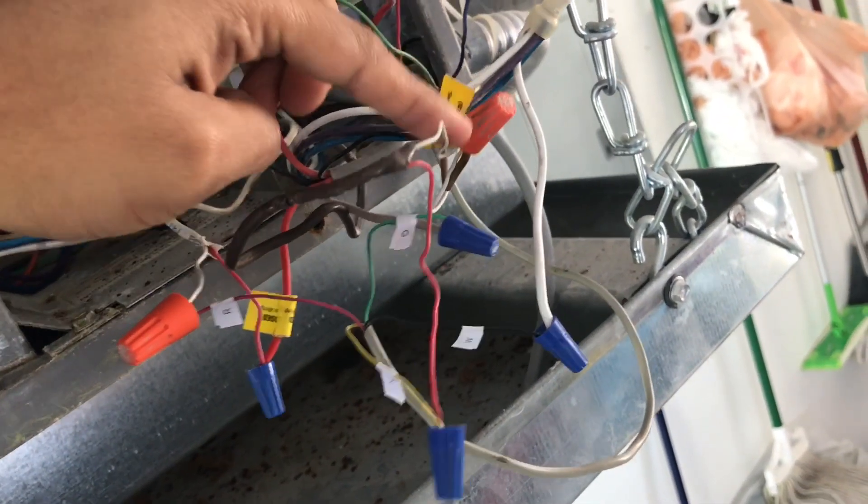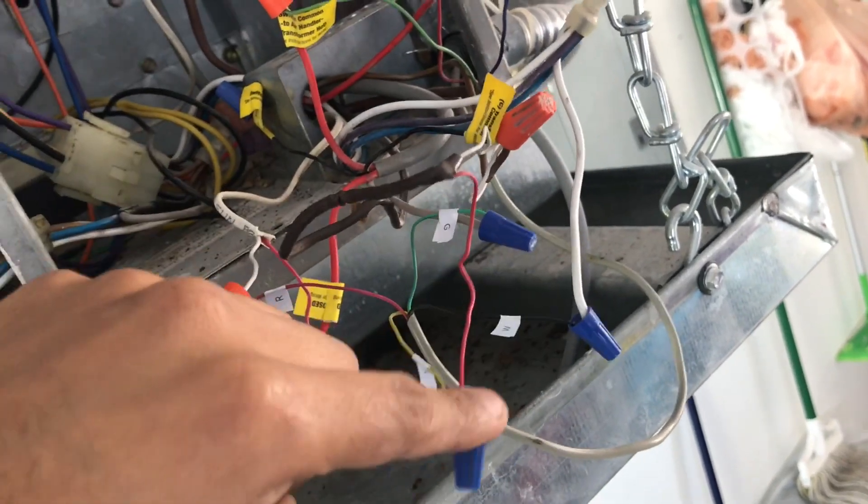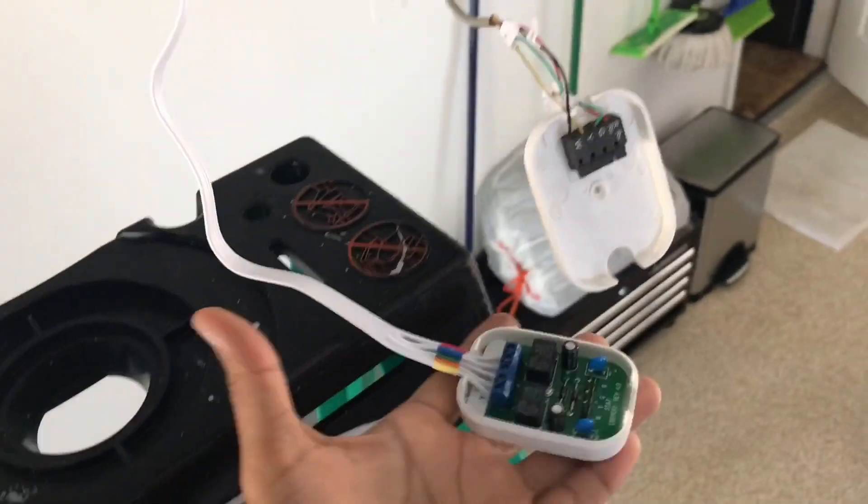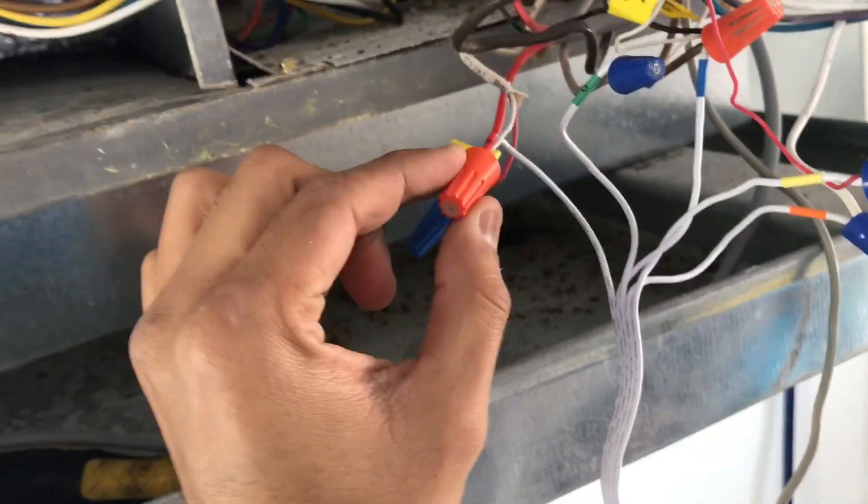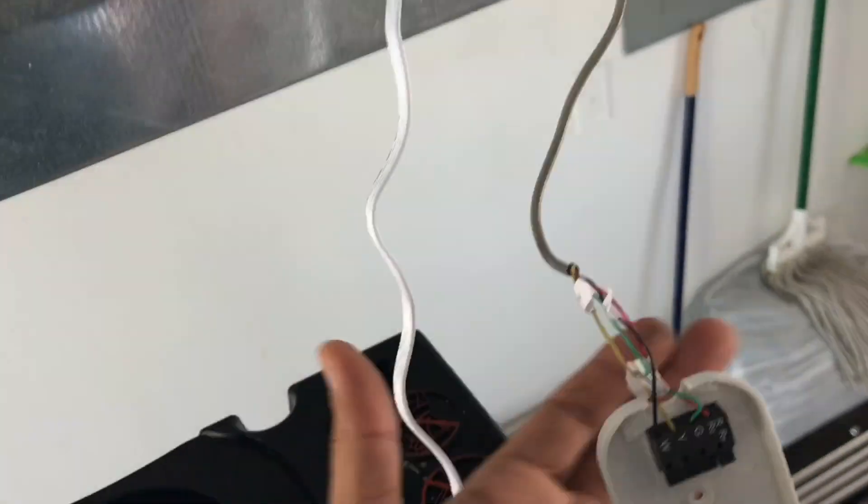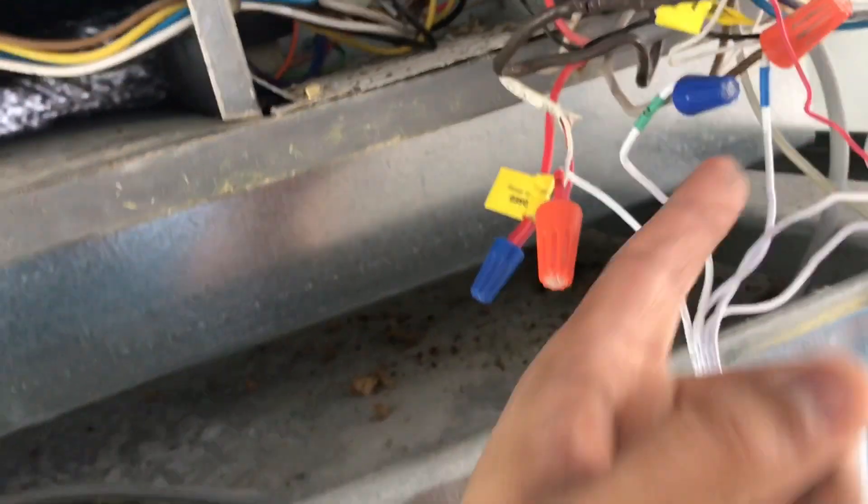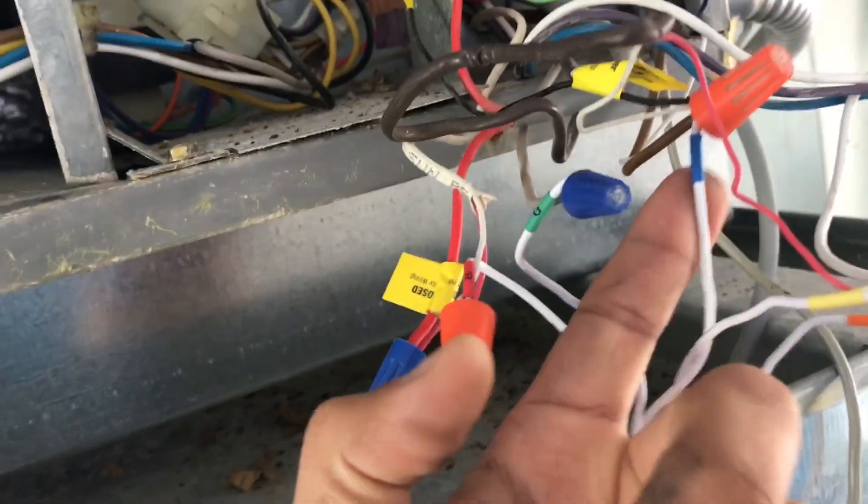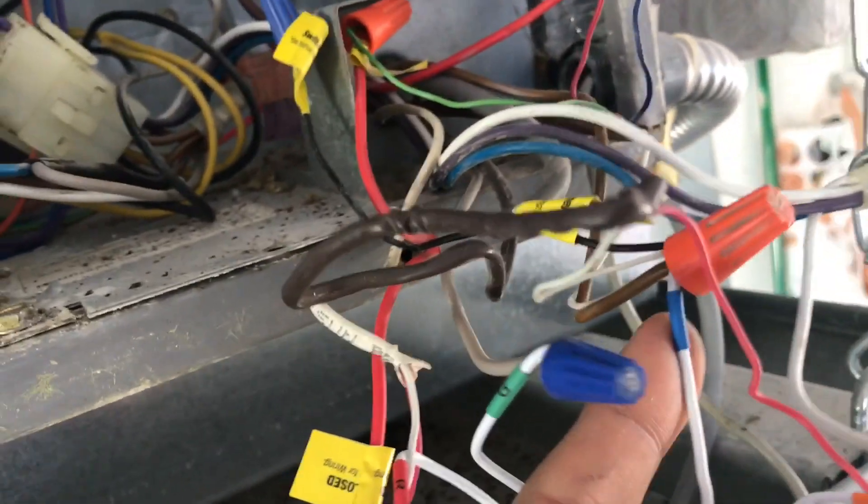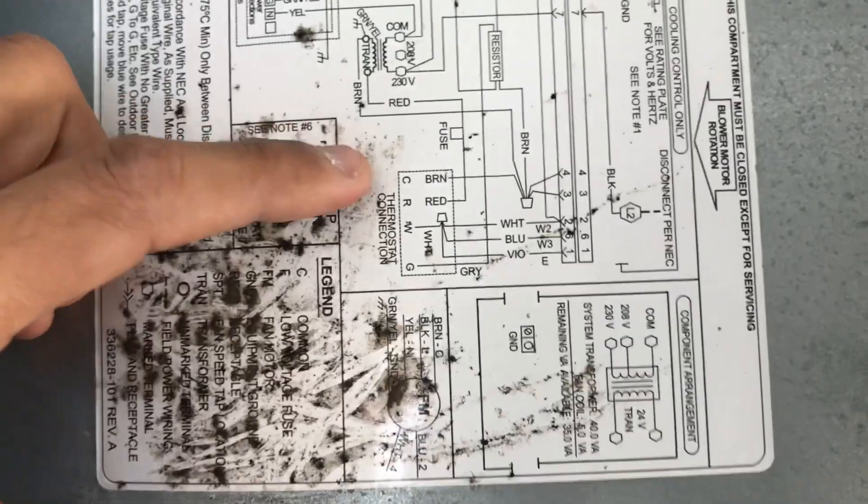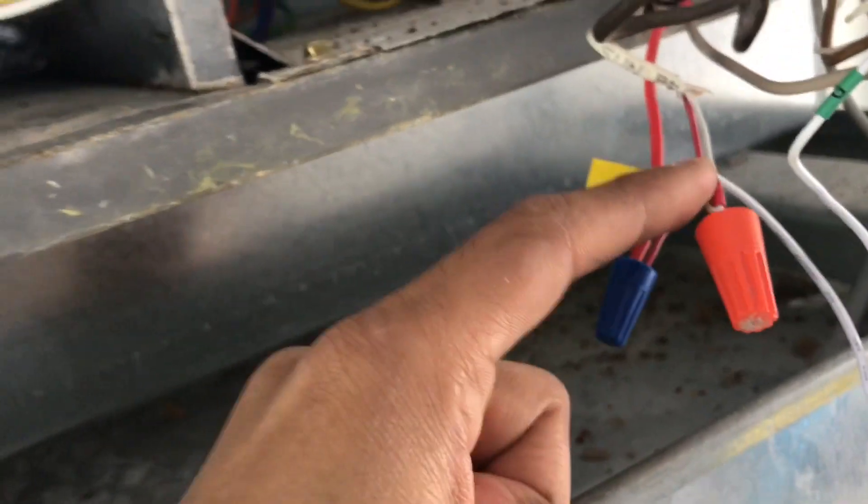One needs to go to the brown, one needs to go to the yellow, and that's it. So the PEK was installed. As you can see, all the cables coming from the thermostat are now in the other half of the PEK. And then everything here, and it's like I said before, the blue should go with the brown or C to brown. Red to red, so we got red here but we got this smoke detector cable, so it's red and it's bridged here into this other cable.